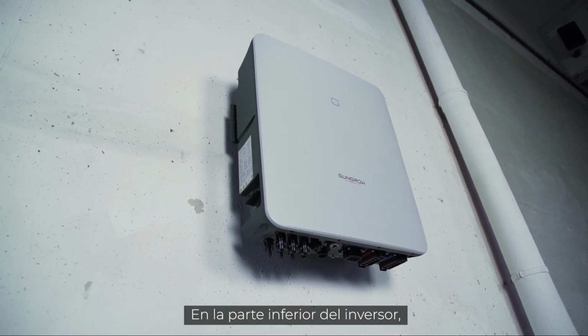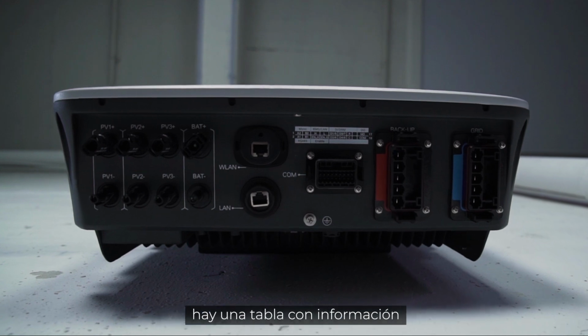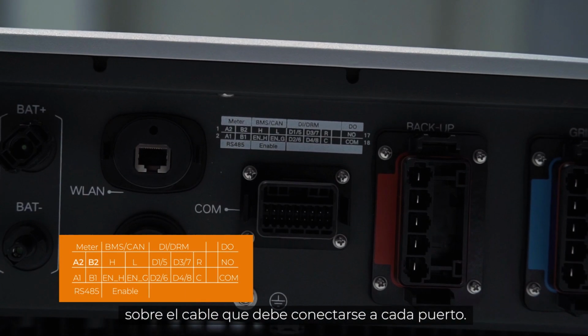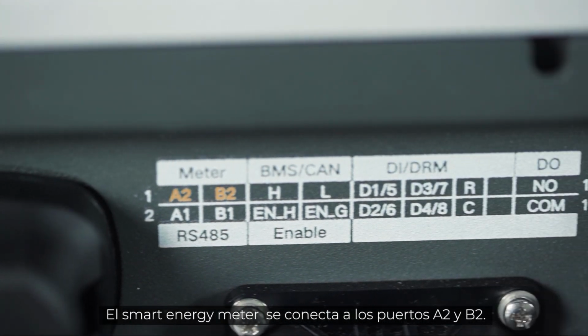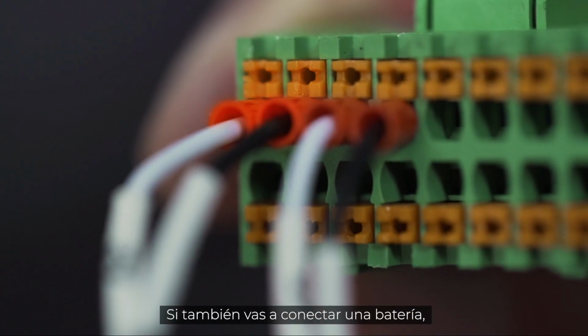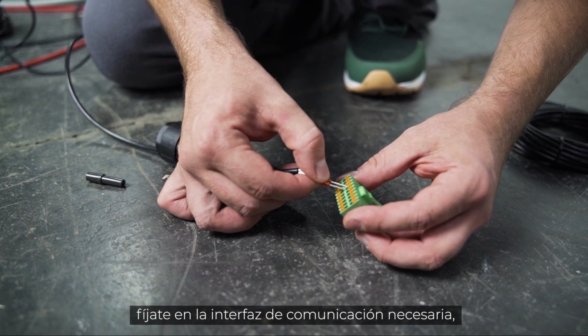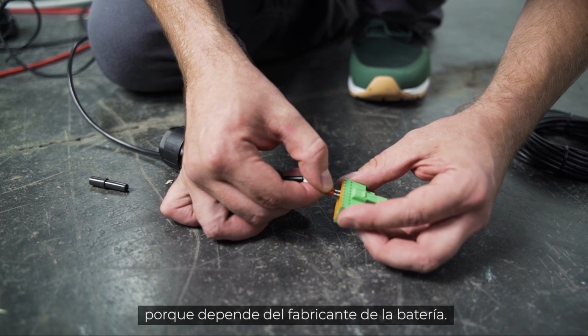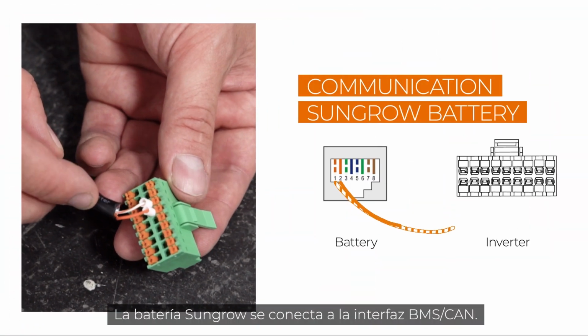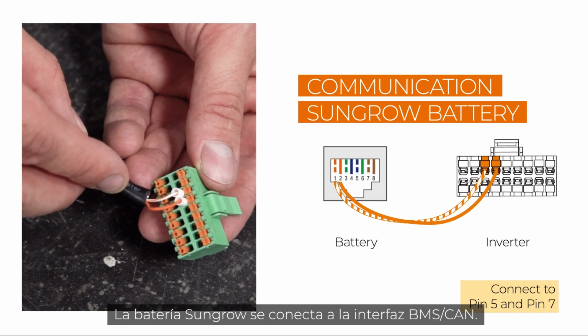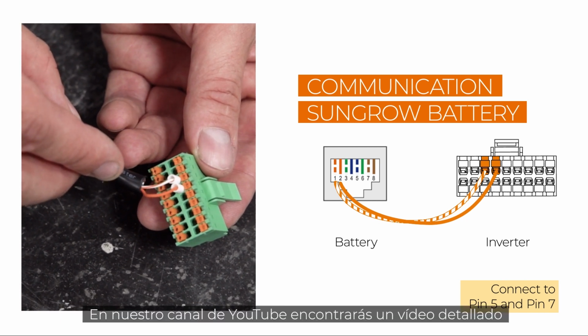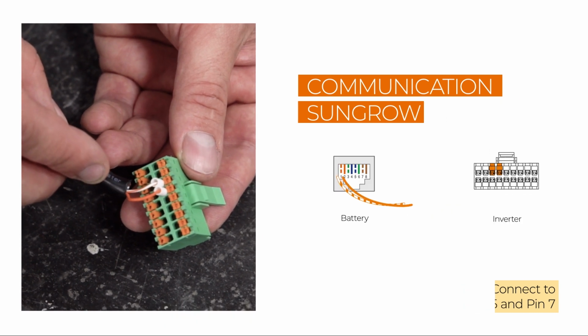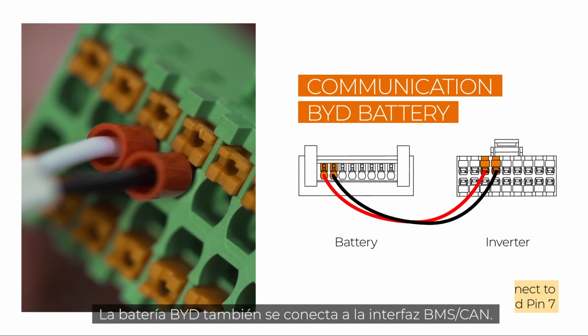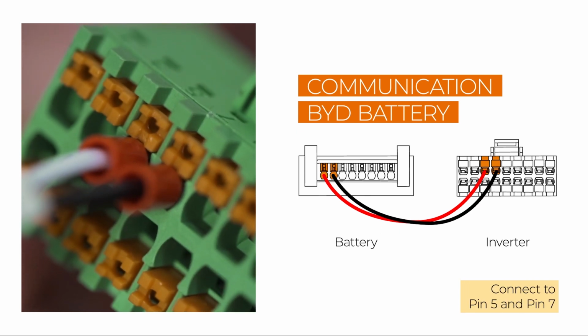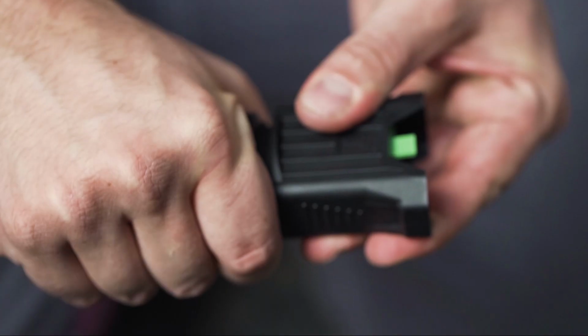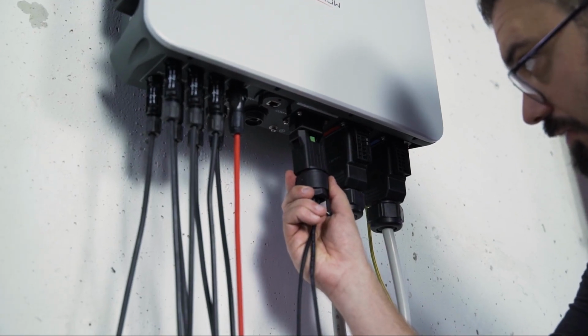At the bottom of the inverter, above the connector for the communication plug, you will find a table with information about which cable has to be plugged into which port. The smart meter is connected to the ports A2 and B2. If you also want to connect a battery, you need to pay attention which communication interfaces have to be used, as it depends on the battery manufacturer. The Sungrow battery is connected to the BMS CAN interface. You may find a detailed installation video for our battery on our YouTube channel. The BYD battery is connected to the BMS CAN interface as well. Plug everything together, screw it, and plug it in.